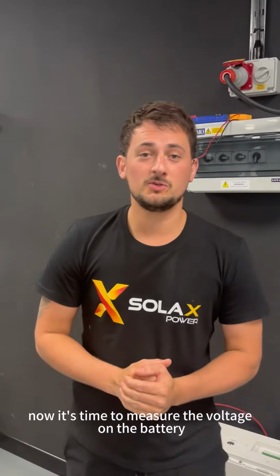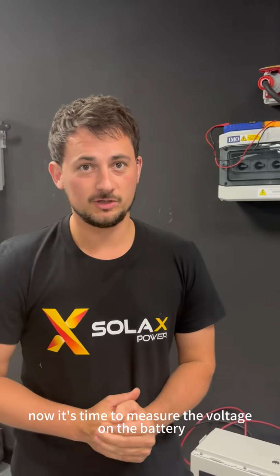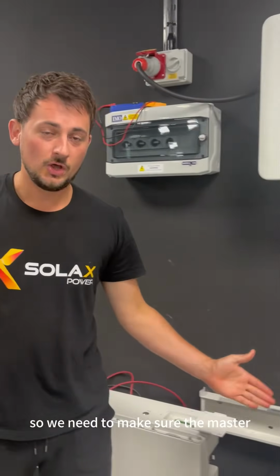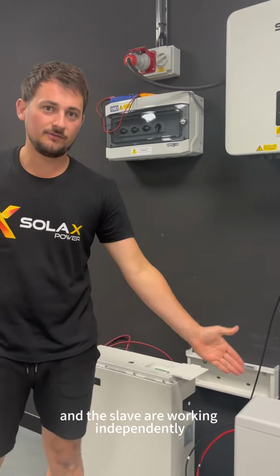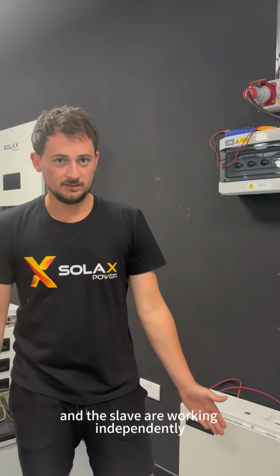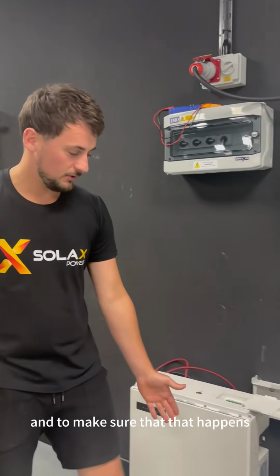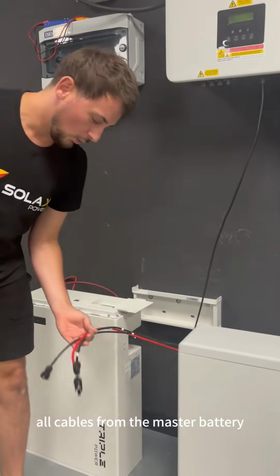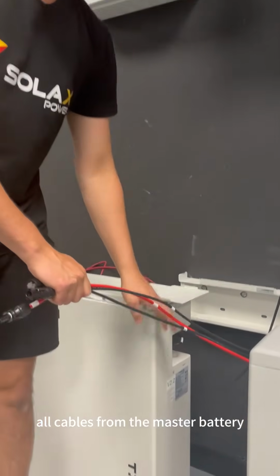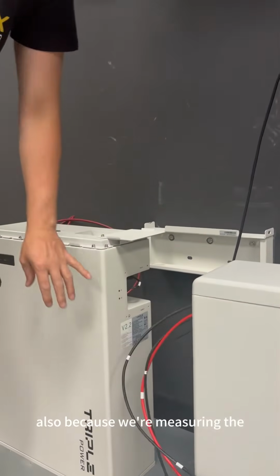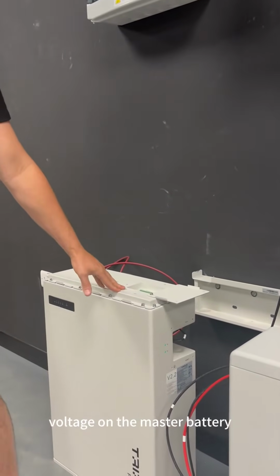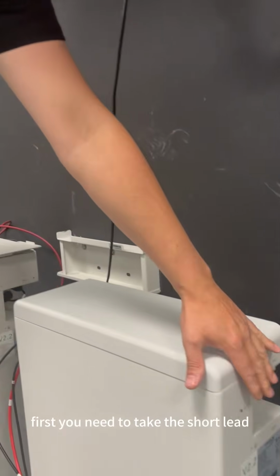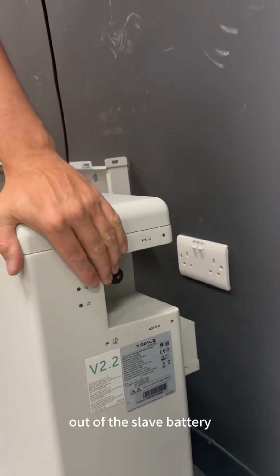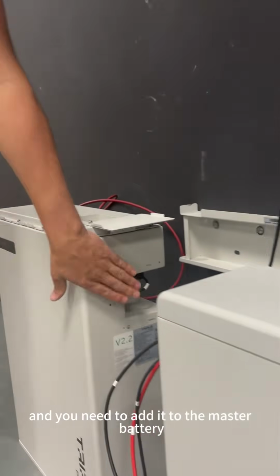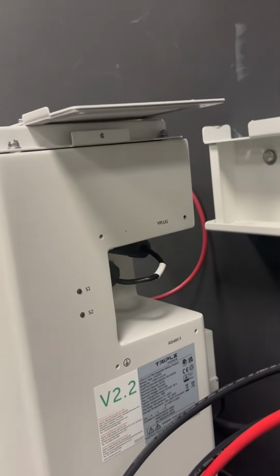Okay, now it's time to measure the voltage on the battery. So we need to make sure the master and the slave are working independently. And to make sure that that happens, you need to disconnect all cables from the master battery. Also, because we're measuring the voltage on the master battery first, you need to take the short lead out of the slave battery and you need to add it to the master battery.